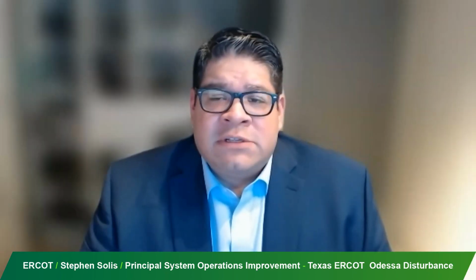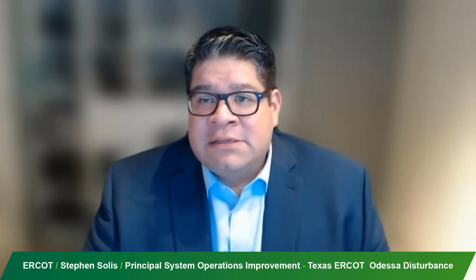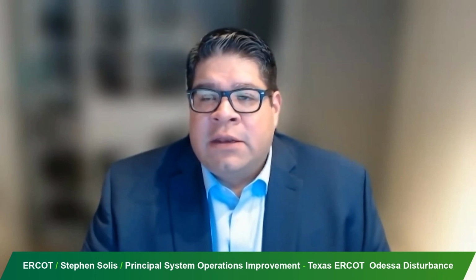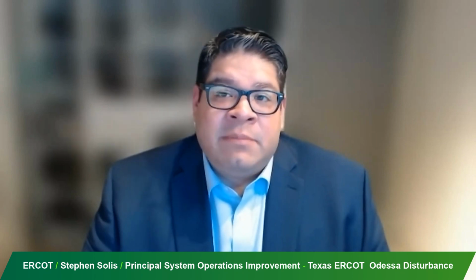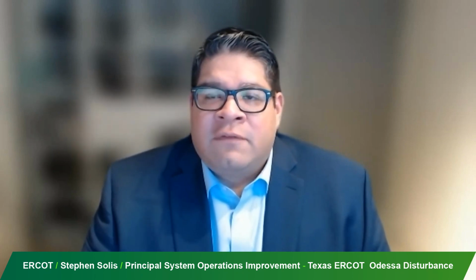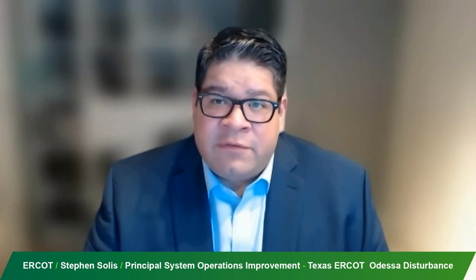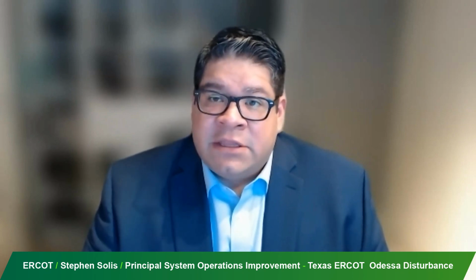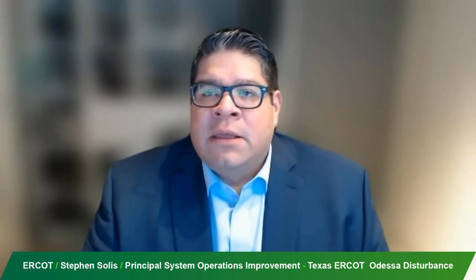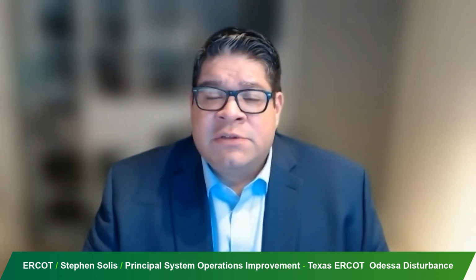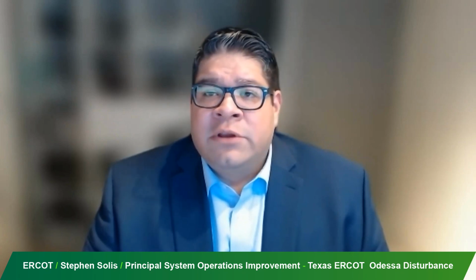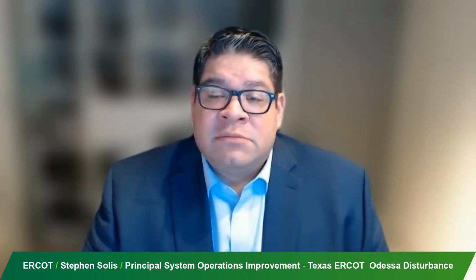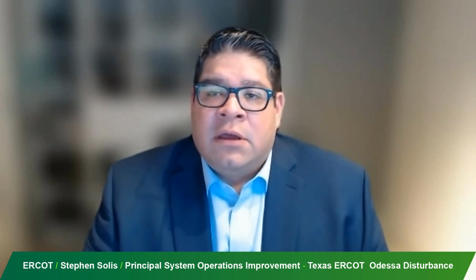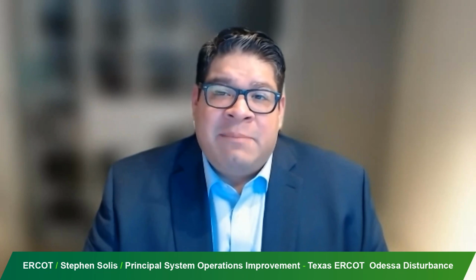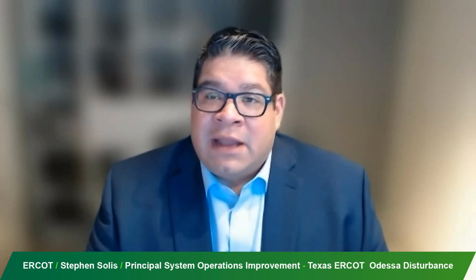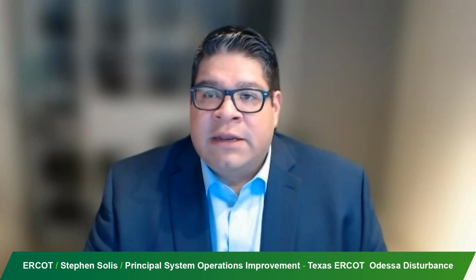Yeah, I think positive sequence models have definitely played a significant role. I think when you look at inverter-based resources, the EMT models, the very detailed models, offer you the ability to screen for things like this, because you actually get the control level type modeling. Obviously, you mentioned system strength issues. That's also going to be helpful when you're trying to really see how these systems are interacting and controlling with these inverter-based resources. That being said, it's really important that not only do you have EMT models provided, but that they're good models and that they match what's actually being implemented in the field.